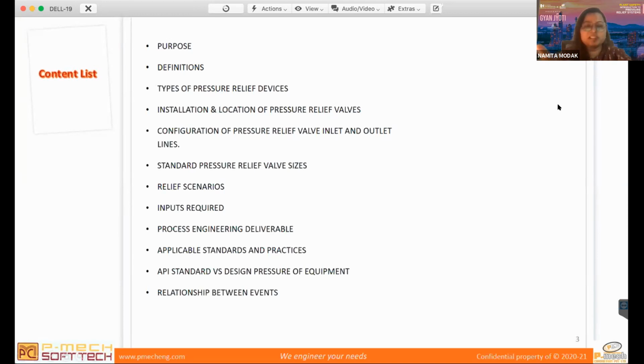MAWP is called the maximum allowable working pressure. One thing is the design pressure. Based on the design pressure, you give it to mechanical, and mechanical selects the thickness of your vessel, for example. Let's say I have a design pressure of 60 bar gauge, but the corresponding thickness for that 60 bar gauge comes to something like 10 mm, but he selects 18 mm instead of 10 mm. So whatever pressure he gets considering 18 mm is called the maximum allowable working pressure, which is more than your design pressure in this case. Normally the maximum allowable working pressure is equal to your design pressure, but it can be more than your design pressure as well, as in the case I just explained.